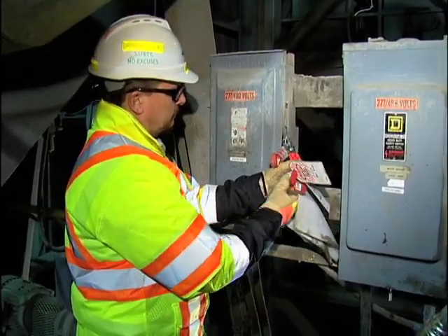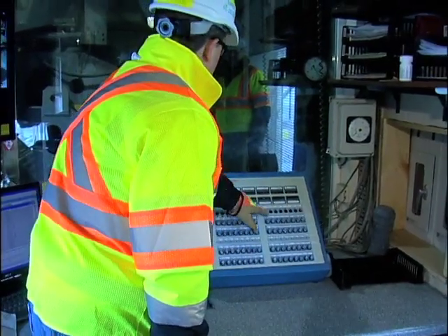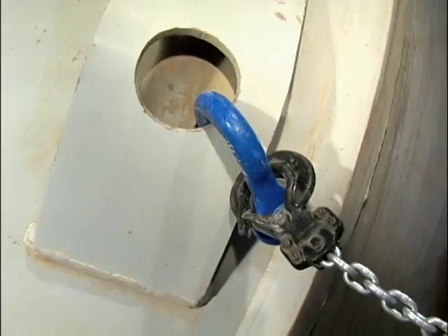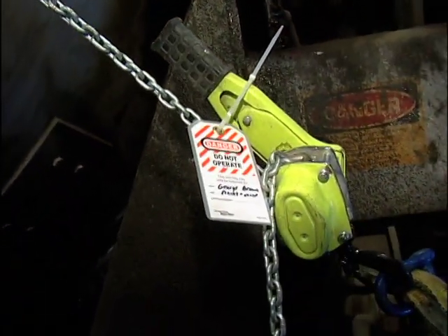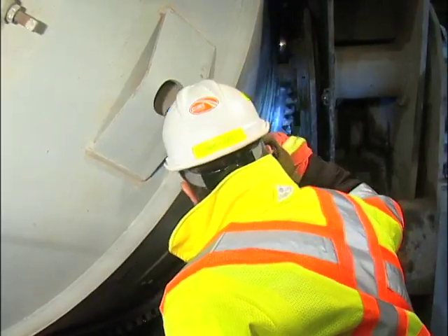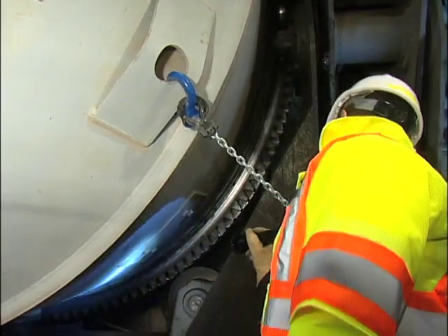Additionally, the activities cover making adjustments or tool changes to equipment at a ready-mix concrete plant, in which the employee may be exposed to the unexpected energization or startup of the equipment, or there's a release of hazardous energy. What are the proper lockout, tagout procedures for this area? I would throw these 2 disconnects. I would turn this water off and check here for the pump to come on.